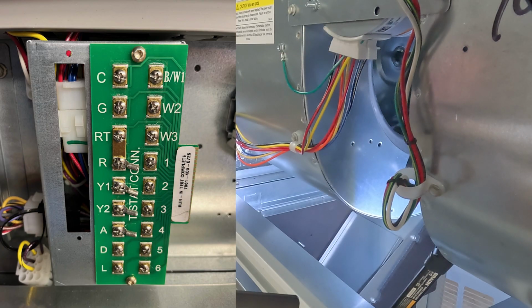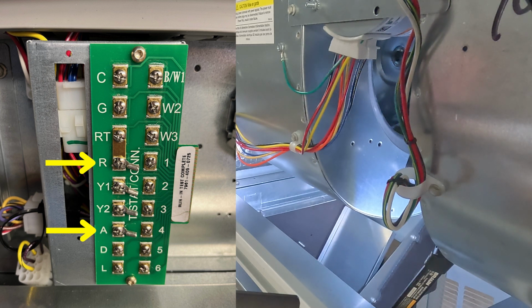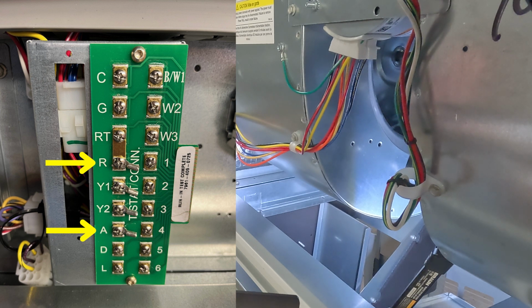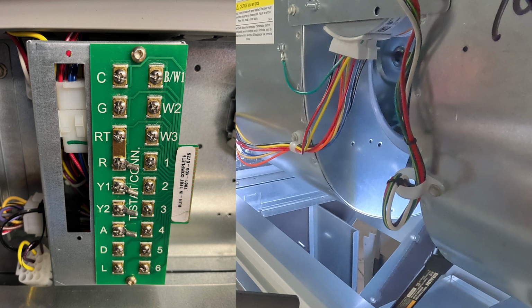With power to the unit and both screw stops in the correct position, jumper wire R to A on the low voltage terminal block. This will energize the damper actuator, but not the indoor blower motor with this CRV. The damper will stop where the screw is inserted at blade stop 5, which will take about 20 seconds. Remove the jumper wire on A and the actuator will spring load closed.